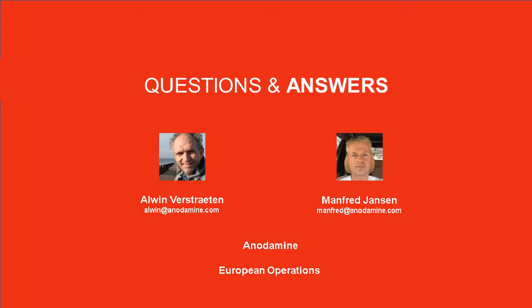Well, as we have shown in the presentation on the Polish plant, which has been using phosphate and oxygen scavenger, we successfully transferred it to anodamine and ammonia treatment. So the answer is basically a no. The transfer from one chemistry to another may be different from one conventional treatment to another one. And there is no specific need to prepare the system before anodamine can be started.